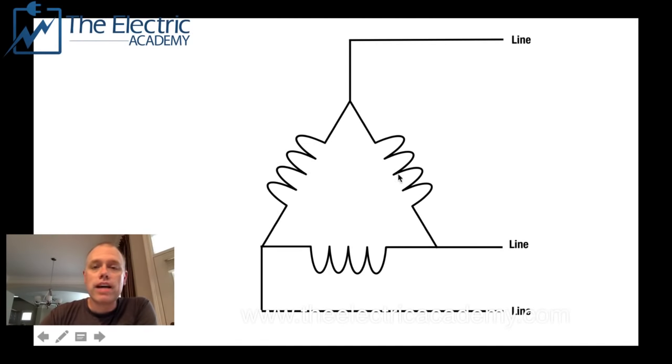Now this is the delta system. The delta system is a bit different than the Y in the fact that if you notice line to line here, it's just across a phase. So your line and your phase voltage are the same voltage. So if this is 120 volts, your line to line is 120 volts. So there's that.